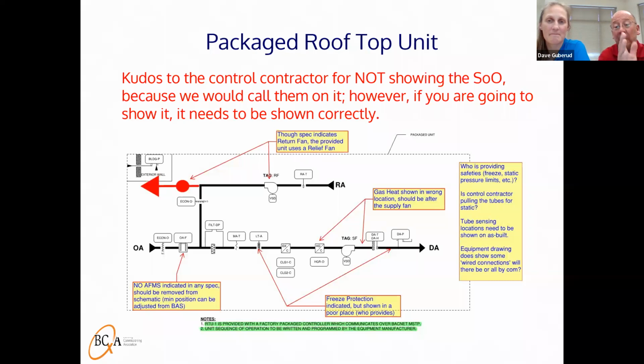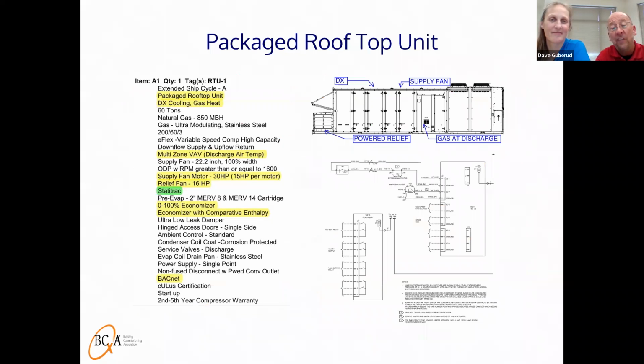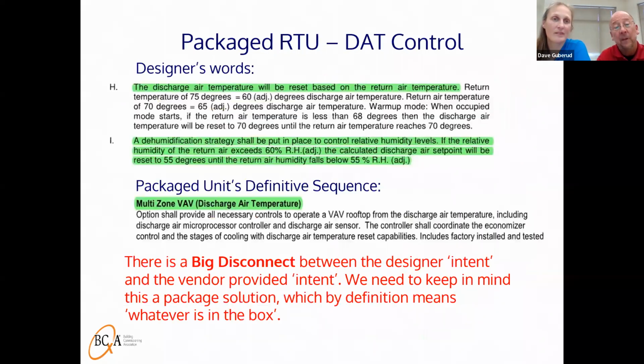So between looking at a schematic, which should be done accurately, and then the next page, please, going over the submittal to make sure how things operate and that the devices being provided are all little cross checks. Which leads us to making sure that the designer's words and the submitted words reconcile. Here they're telling the designer that discharge air temperature reset will be based on return air temperature, and they talk about dehumidification strategies. But when you look at the packaged unit sequences, that's not what they're doing. There's a disconnect between them.